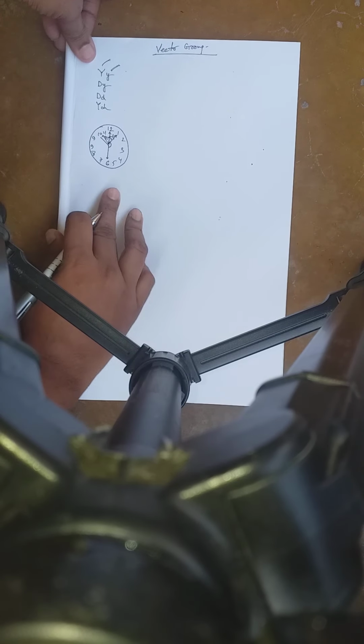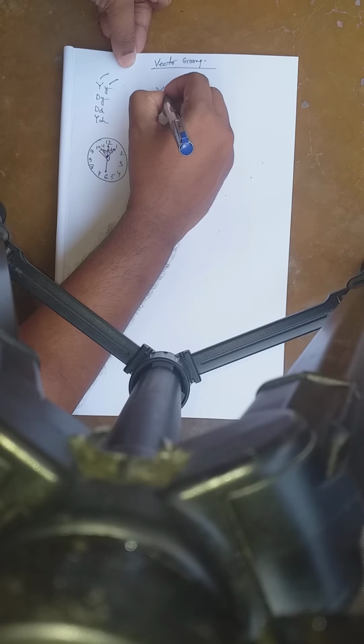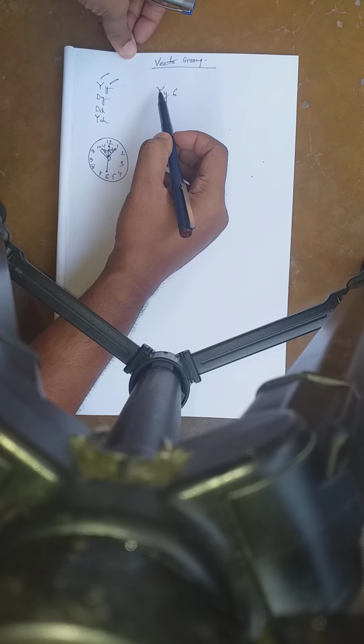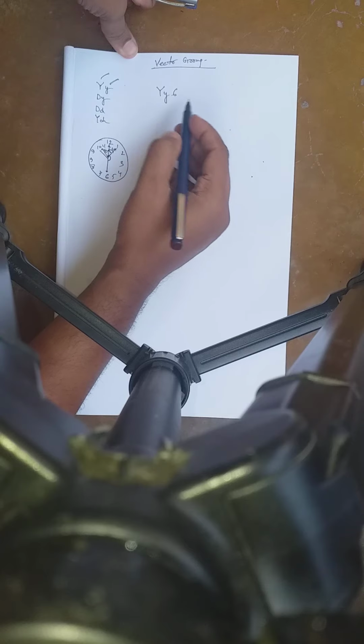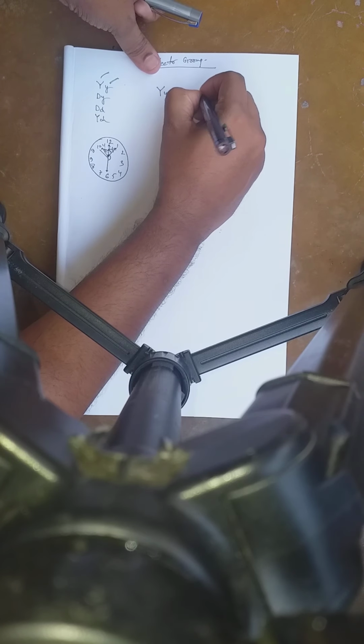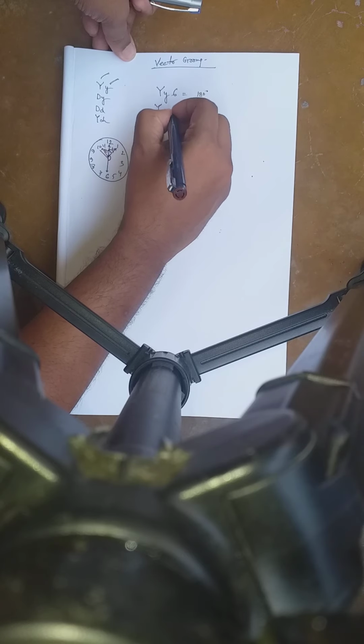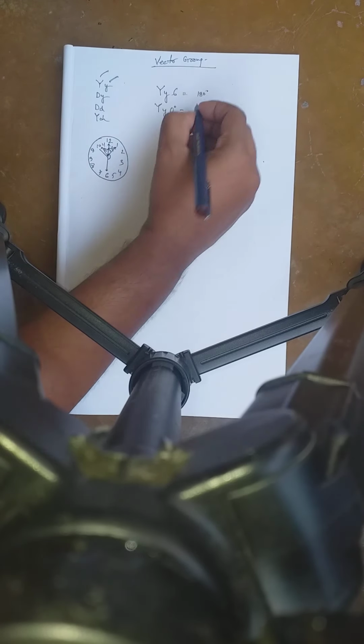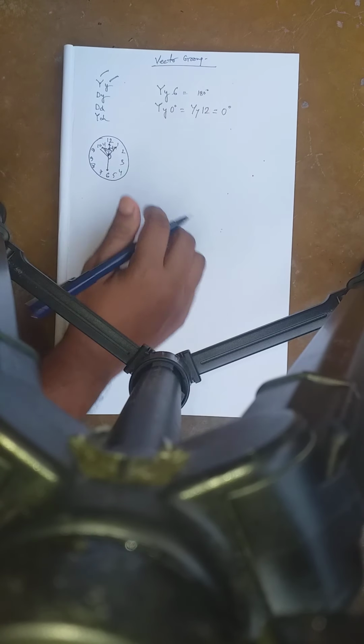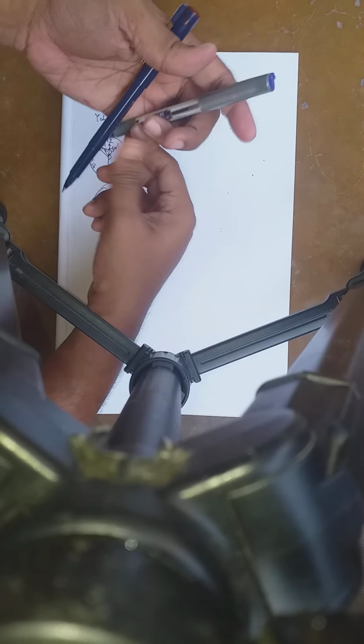So we can write Yy6. That means the displacement between the primary winding and secondary winding is 180 degrees. Suppose Yy0, or Yy12, then the displacement or difference between primary winding and secondary winding is 0 degrees. This is 12, this is 6, 180 degrees. If both are in the same direction, that is 0 degrees.